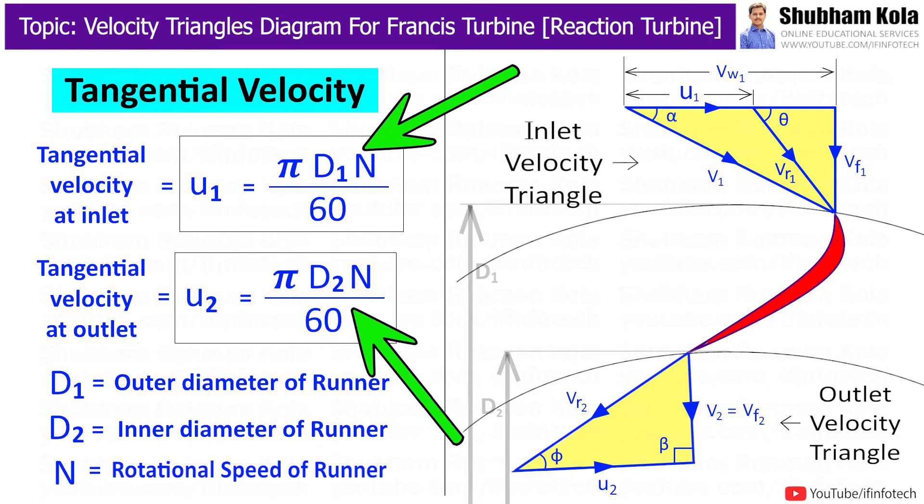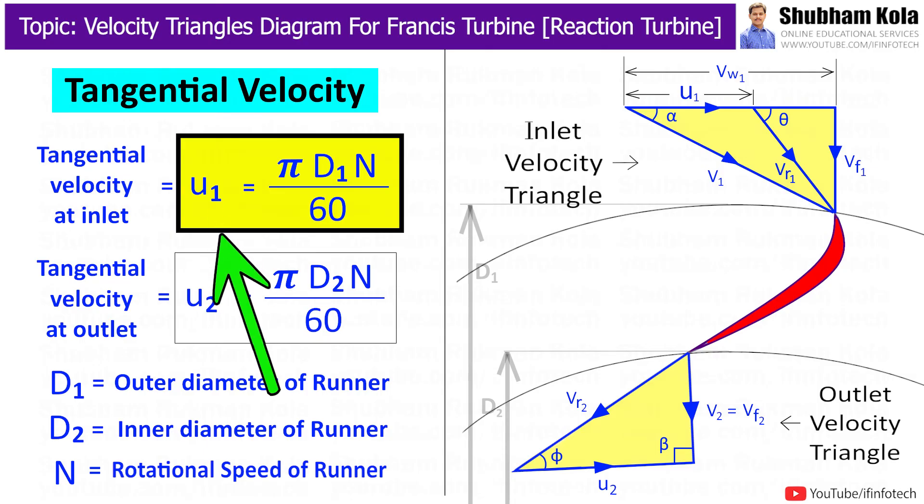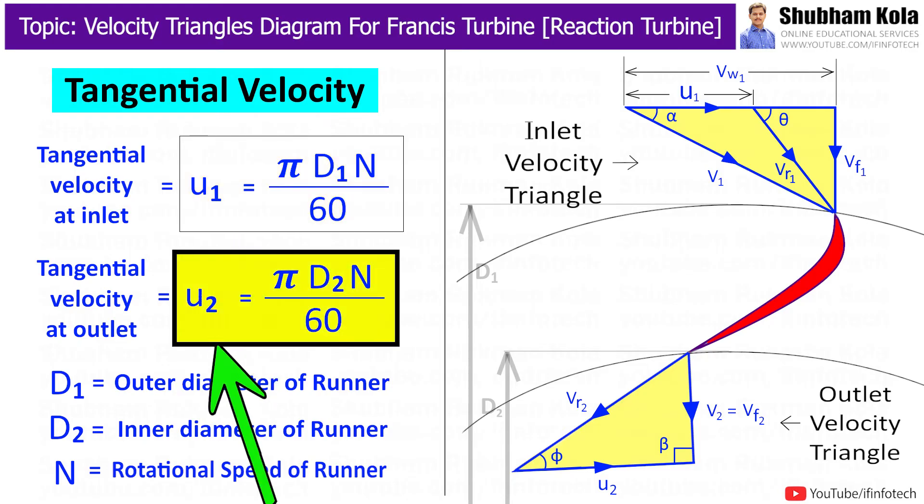Now here d1 and d2 are the outer and inner diameters of runner rotating at n rpm. So, tangential velocity at inlet is denoted as u1 and is given by formula pi d1 n by 60. And tangential velocity at outlet is denoted as u2 which is given by formula pi d2 n by 60.